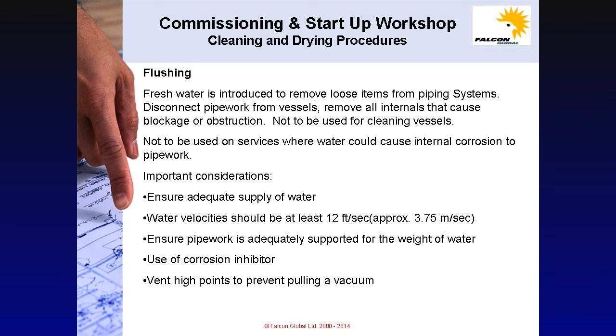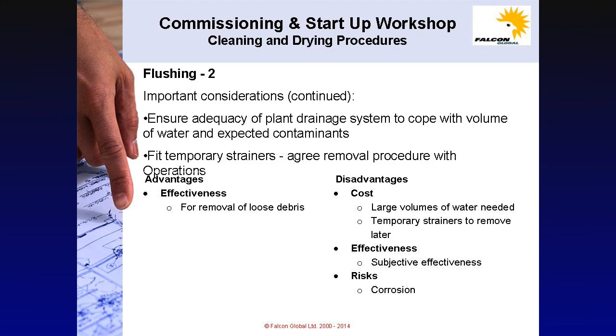Ensure the pipework is adequately supported for the weight of water and use a corrosion inhibitor. Vent all high points to prevent pulling a vacuum. Ensure the adequacy of plant drainage systems to cope with the volume of water and the expected contaminants. Fit temporary strainers inside the pipework and agree the removal procedure with operations for a later date. The advantages of water flushing are its effectiveness for the removal of loose debris, but its disadvantages are also its cost. Where large volumes of water are needed, the requirement to install temporary strainers that will need to be removed later by operations, and its effectiveness, because this is very subjective. There are also the risks of corrosion.